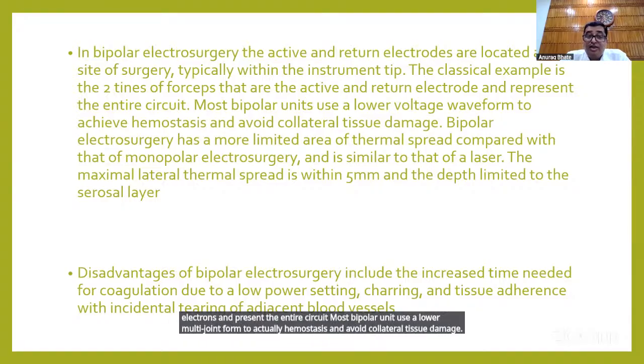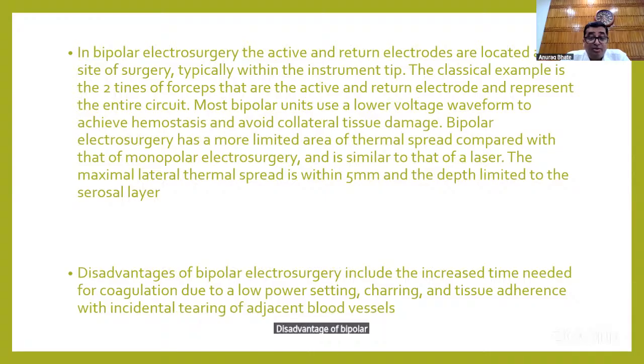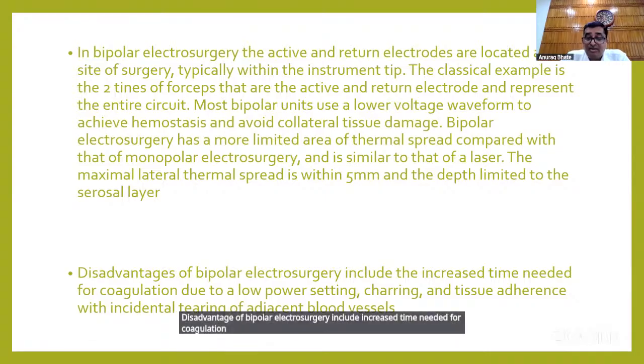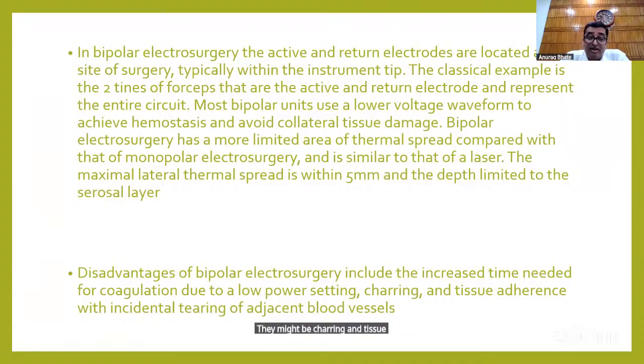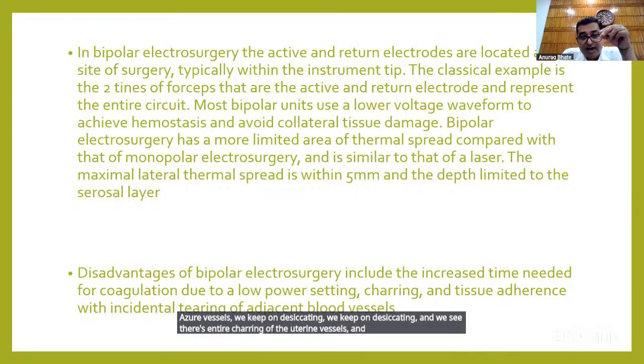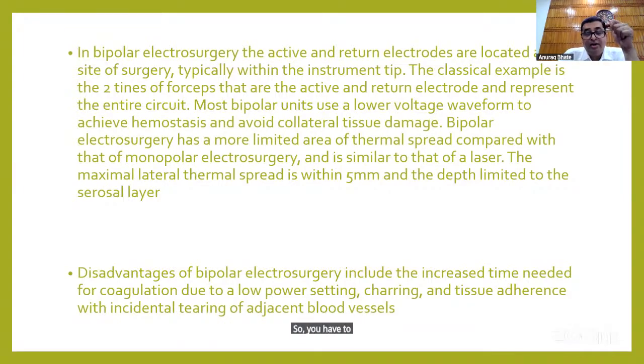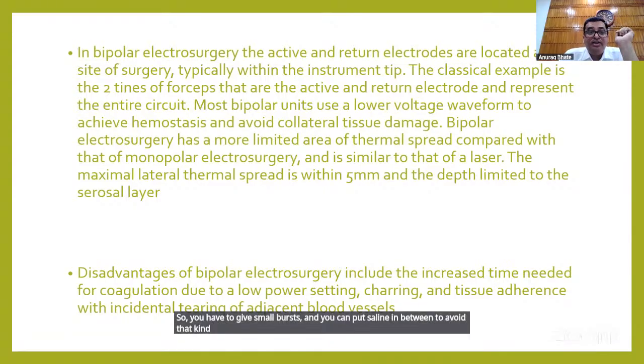A bipolar electrosurgery has a more limited area of thermal spread compared to that of monopolar and is similar to that of laser. The maximum thermal spread is within 5 mm and the depth limited to probably serosal layer. Disadvantages of bipolar electrosurgery include increased time needed for coagulation due to low power settings. There might be charring and tissue adherence with incidental tearing of adjacent blood vessels. This we have seen when we still use bipolar for uterine coagulations and larger vessels. We keep on desiccating and keep on desiccating, and we see there is an entire charring of the uterine vessels. And when you remove the bipolar, the entire tissue gets adhered to it, and the blood vessel just opens up or tears. So you have to give small bursts, and you can put saline in between to avoid that kind of adherence to the blood vessel.